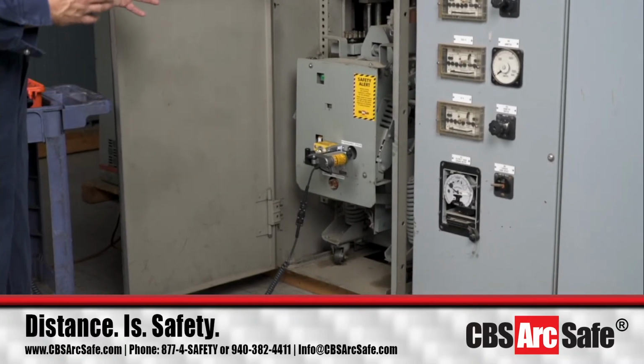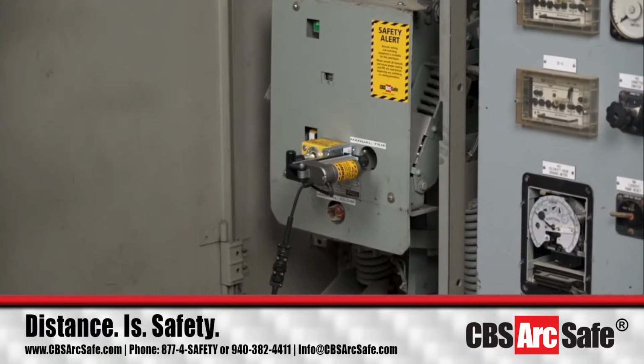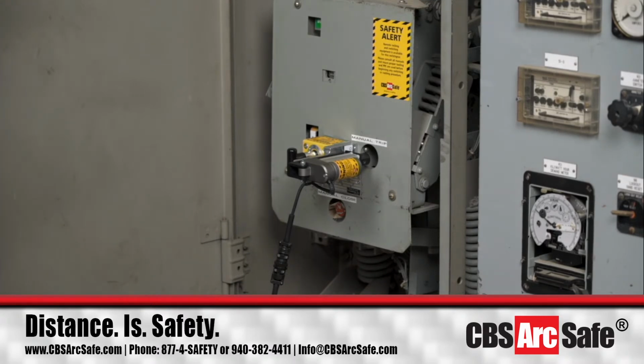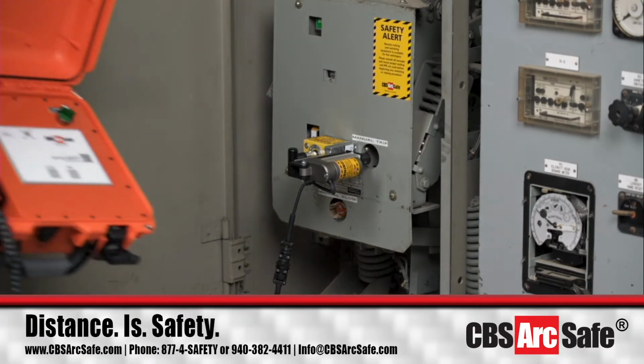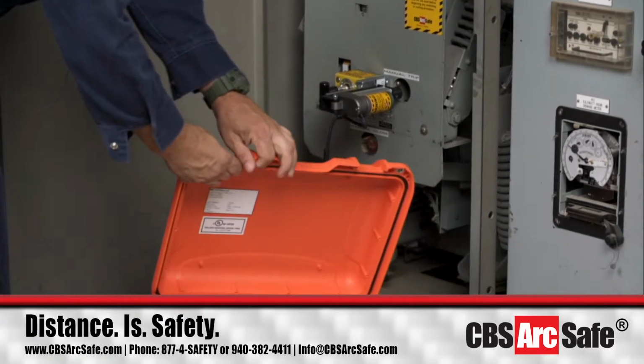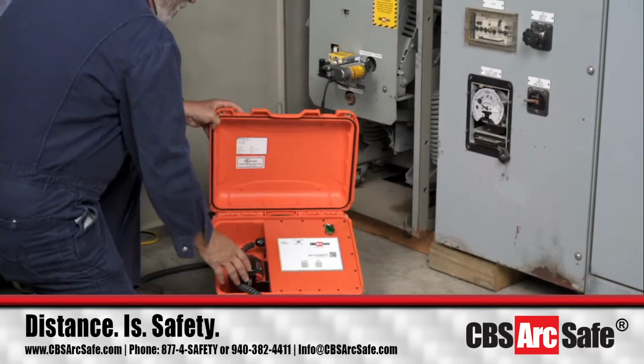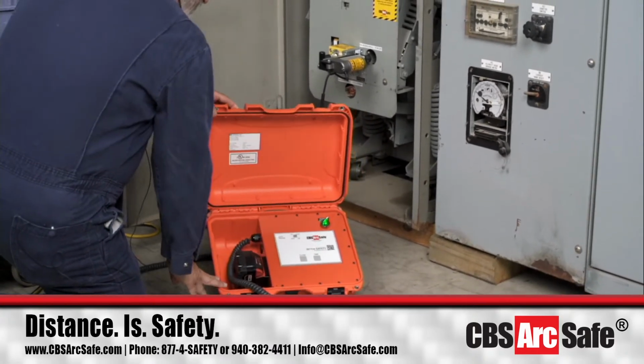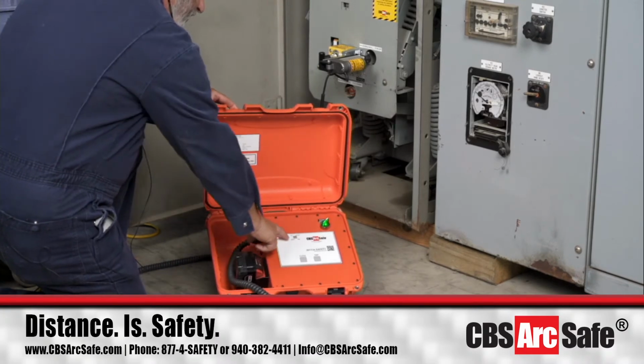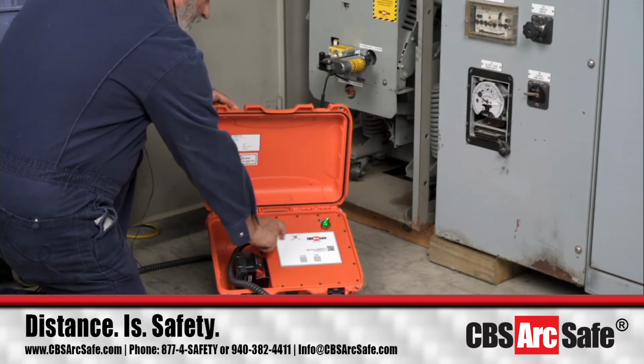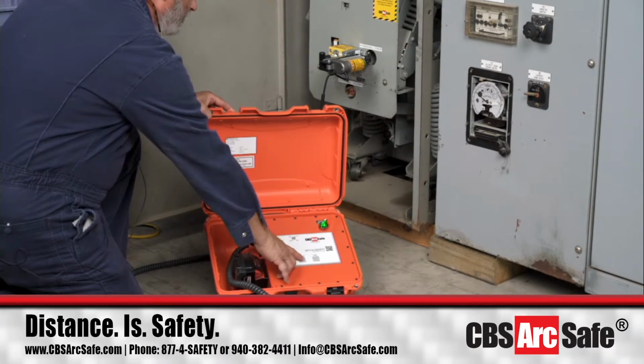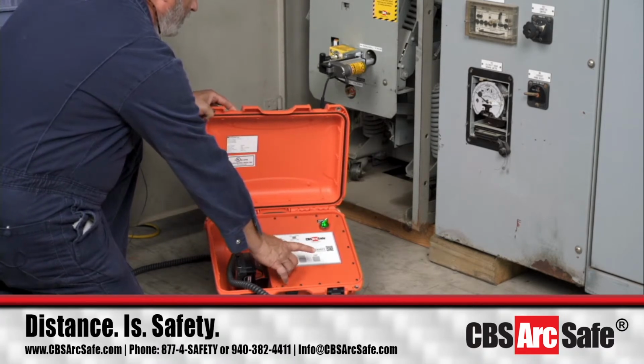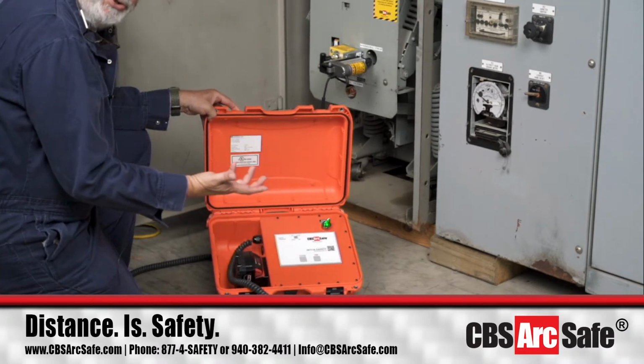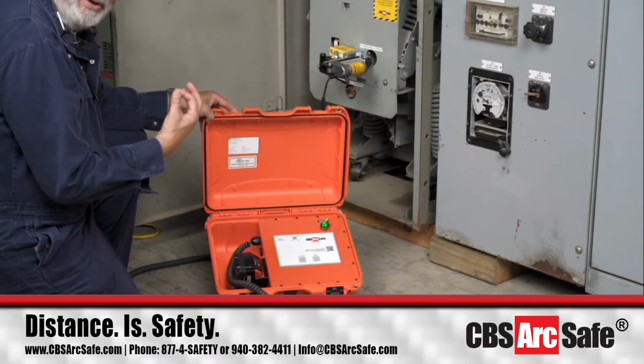Now I don't have the ability to charge and close and trip this breaker today, but I can still show how this works. So I'm going to pull up the RS-01. I'll tell you what I'll do. I'll put it down here so that we can see everything operate at the same time. Okay, so I'll turn it on. For this particular actuator, we have to have close AR selected, and we're going to push down the close button, and it's going to go in and it would actually trip the breaker like that, and you'd hear the bang.